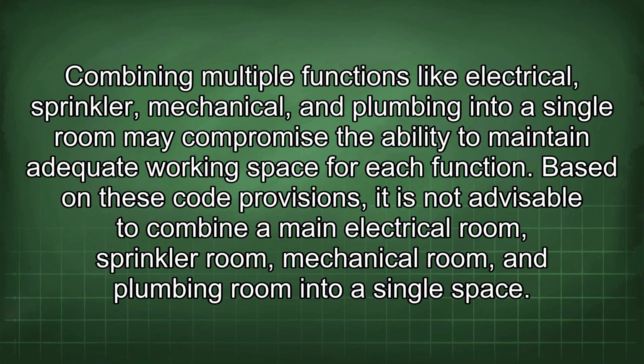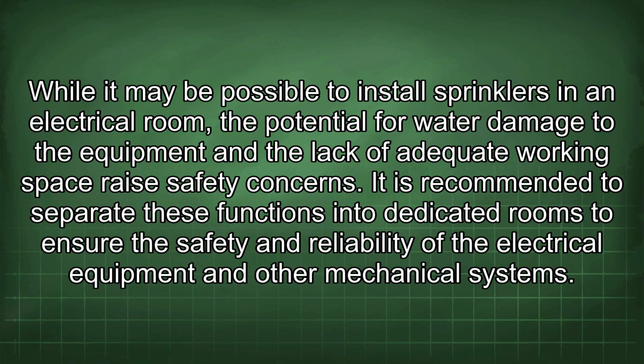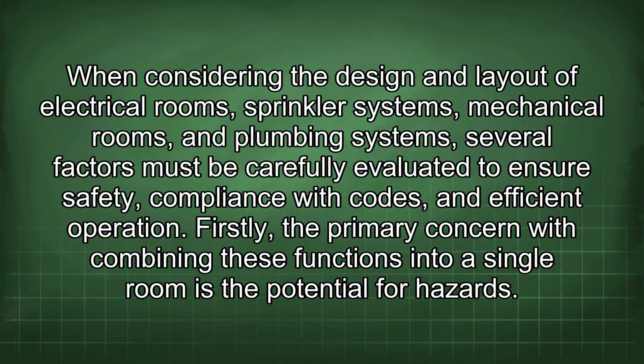Based on these code provisions, it is not advisable to combine a main electrical room, sprinkler room, mechanical room, and plumbing room into a single space. While it may be possible to install sprinklers in an electrical room, the potential for water damage to the equipment and the lack of adequate working space raise safety concerns. It is recommended to separate these functions into dedicated rooms to ensure the safety and reliability of the electrical equipment and other mechanical systems.